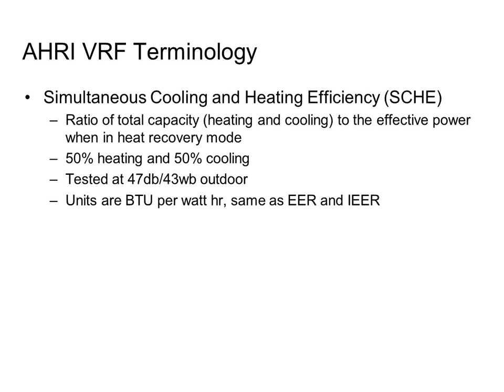The SCHE is the ratio of the total capacity, meaning all the heating BTUs being delivered to zones plus all the cooling BTUs being delivered to other zones, as related to the effective power when it's in that mode. For that particular test, they're assuming 50% of the zones want heat and 50% want cooling. So basically nothing's getting rejected outside. So it's the best possible case in time, like we showed before. This test is done at the 47 degree point. They don't do it at the 17 like the heating does, probably because they figure if half your zones need cooling, it's probably not 17 outside, so no reason to do the extra testing.